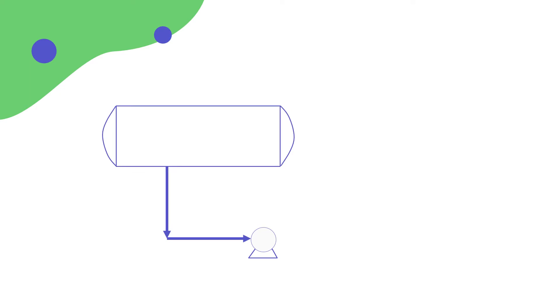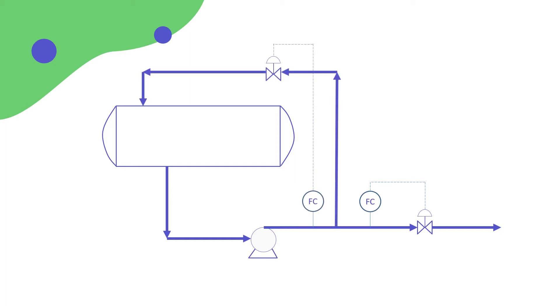Hello everyone. Suppose we have a pump that draws some fluid from a vessel. The pump flow is controlled on the discharge line and there is a minimum flow controller. We need to specify the pump for this operation. In order to specify a pump correctly, we need to carry out several calculations: specify its NPSH, determine the pump differential pressure and hence the differential head, and calculate its power. After we have specified the pump data, we shall ensure that the pump is placed in a system that guarantees smooth pump operation, which would be shown on the pump P&ID.